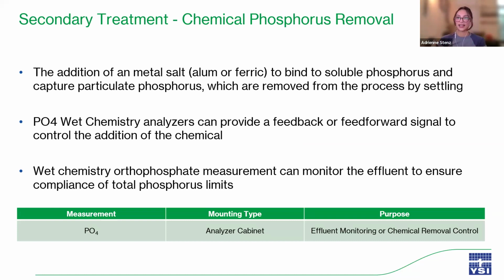Another part of secondary treatment is phosphorus removal. Phosphorus can be removed either biologically or chemically from wastewater. Chemical phosphorus removal requires dosing a metal salt such as alum or ferric, which binds to soluble and particulate phosphorus in the water, creating a solid flock, which is then settled out in the next step in secondary clarifiers.